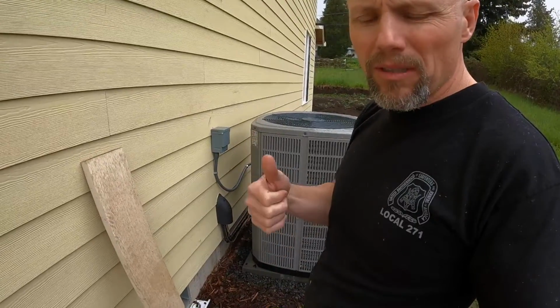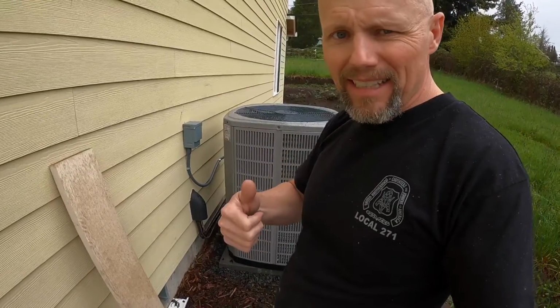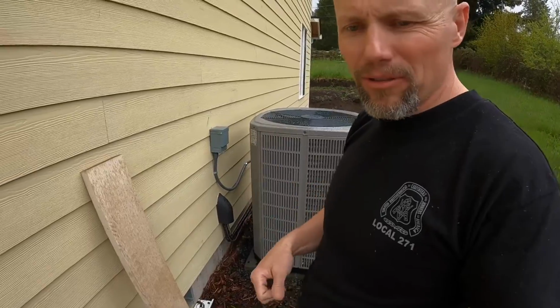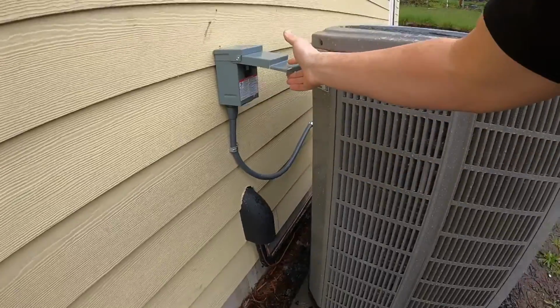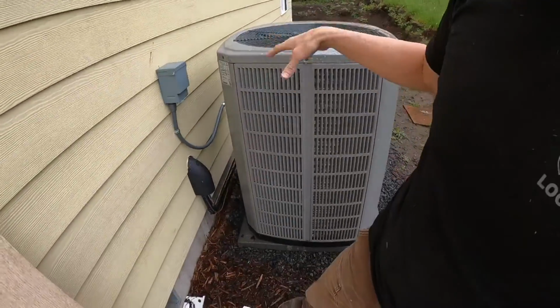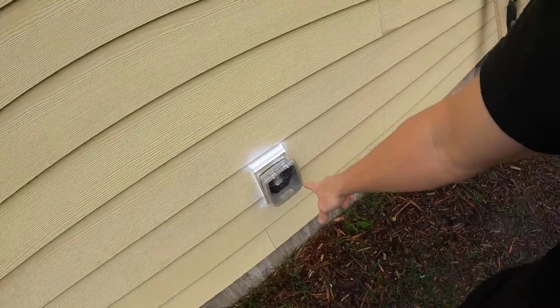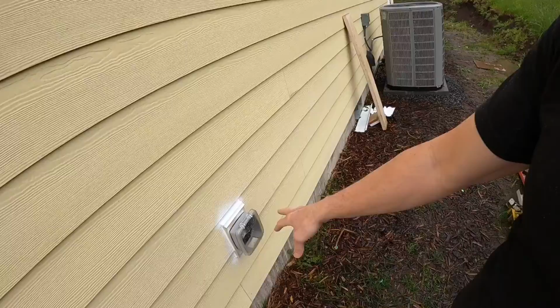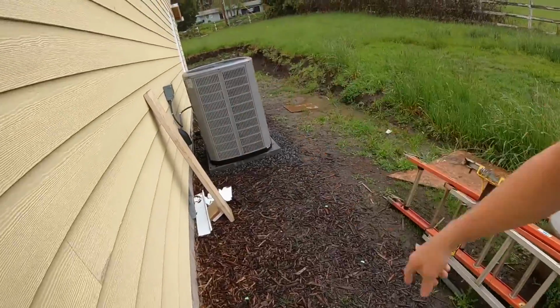They won't do the electrical until certain things are all hooked up so they can run their lines. So the second to last inspection is the final electrical inspection. They hook it all up. They got a breaker out here so that when they're doing maintenance, they can work on it. I believe it's within 20 feet. You also have to have an outlet. So we had to add this because the distance to the nearest other outlet was too far. So we added this for that. So that all has to tie in for an inspection. All right. Now, as far as final electrical goes.